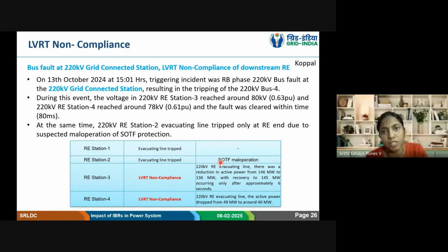Immediately we want the line to trip. So that is called switch on to fault condition. It will basically see the breaker close. This particular function will be active only for some time from the closing of the breaker, and the logic for this can be either distance or overcurrent. If it is distance, it will be set up to zone 2, zone 1, zone 2.